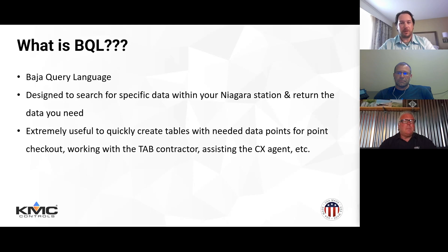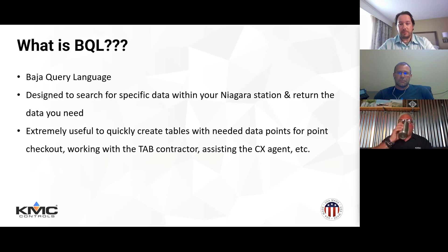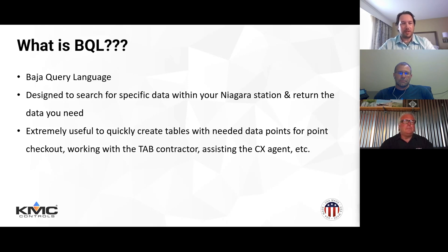Everybody's probably heard of BQL - it stands for Baja Query Language and is used in some form or fashion in Niagara. It's used often programmatically to search for specific data within your station and return groups and tables of data for whatever you need. It's similar to SQL, but not the same and has more limited functionality. It's extremely useful to quickly create tables for point checkout, to see what points might be in alarm, or to search for VAVs that have min or max flow set points at a certain value.